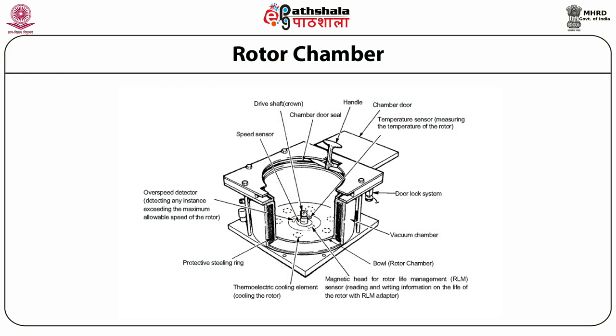The rotor chamber contains many components: thermoelectric cooling elements that control the temperature, a protective steel ring, an overspeed detector that alerts you if speed is exceeded, a speed sensor that measures rotor speed, a chamber door with seal, handles to open and close, a door lock system, a vacuum chamber that provides vacuum, and a magnetic sensor for the rotor. These are the major components of the chamber of a preparative ultracentrifuge.